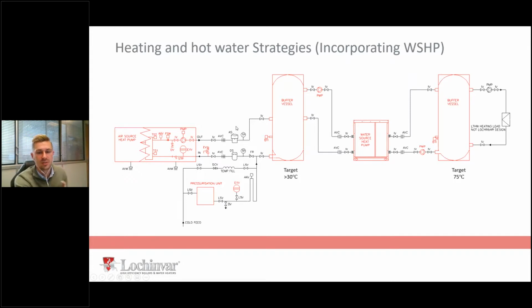Way number one: an air source heat pump serves a thermal store. So the water source heat pump, as far as it's concerned, has a thermal mass at 35 degrees that it can draw on. It thinks its lake is 35 degrees. It thinks we're pulling from a ridiculously warm fjord in Iceland. The water source heat pump pulls energy at 35 degrees, takes it up to whatever temperature we want, up to 80 degrees centigrade, and flows into a buffer vessel, and that buffer vessel connects onto the existing heating system and services our emitters. The emitters are still happy. They're getting the desired temperatures of anything up to 80 degrees centigrade, but we're now doing it with an electric technology and we're doing it efficiently.